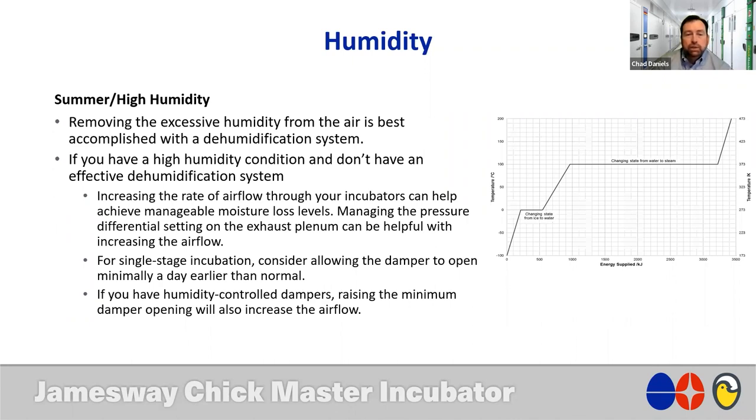Now, an important thing to also point out, I mentioned dehumidification system. Dehumidification works just like humidification. It's the same BTU graph. The only difference is we're doing it in reverse. In order to dehumidify, we have to remove that heat from the air. We have to get that air temperature down to reach saturation. And we have to create an opportunity for that moisture to be removed from that air. And then we have to reheat the air so it's warm enough to be provided to the room and meet our incubation needs. But that's how dehumidification works. It's the same as humidification, it's just in reverse.